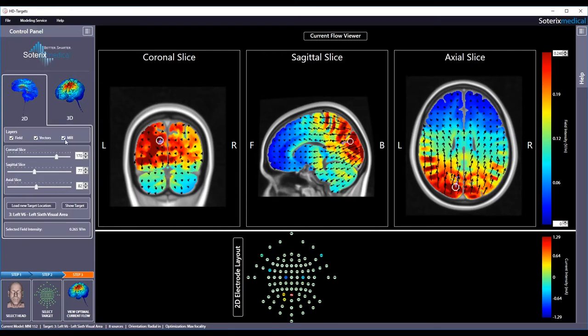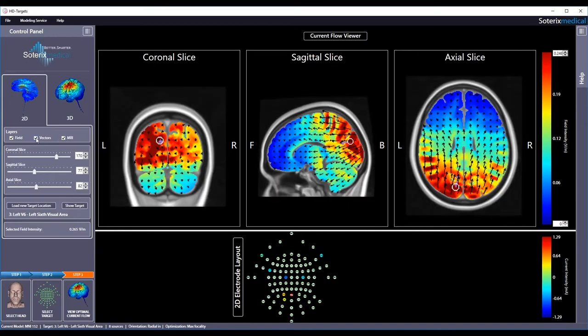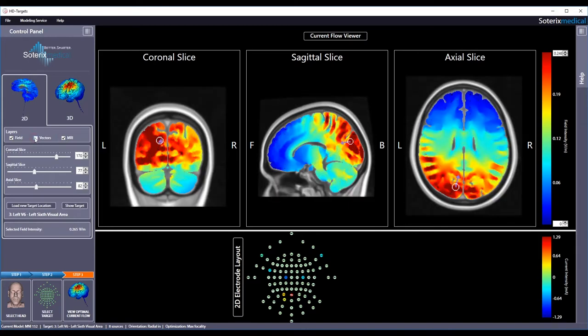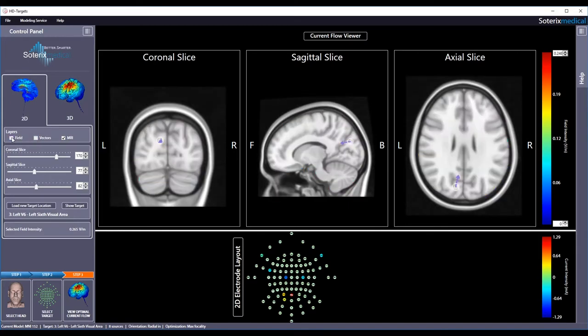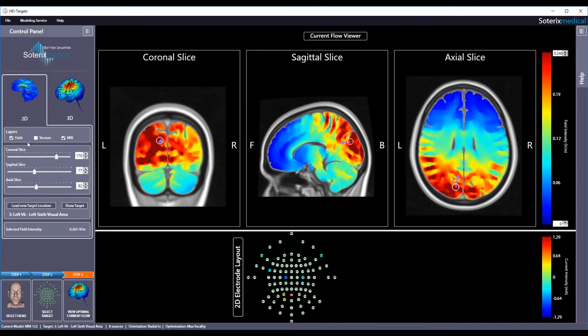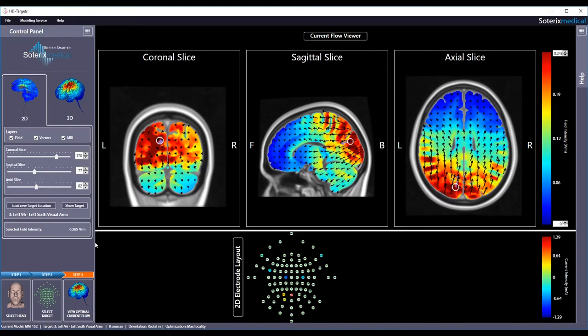You can select to view the subject MRI, the current direction vector or the electric field, or view them all together. The selected field intensity value in the control panel shows the field intensity inside the open white circle or at the target location. An electric field of 0.265 volts per meter is induced at the desired target.